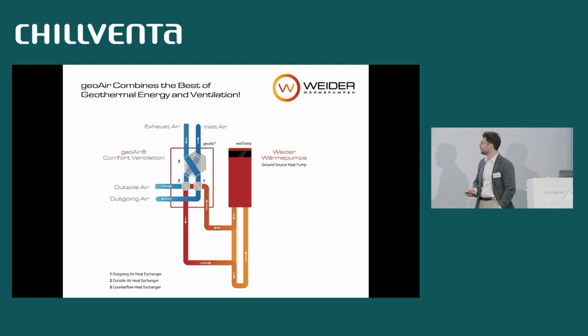You can imagine that in winter, the source temperature is usually between 0 and 5 degrees, and the outgoing air temperature is around 10 to 15 degrees. So there's quite a big delta T throughout the winter, and this enables regeneration of the heat of the geothermal source during the heating period. The second heat exchanger is a brine to air heat exchanger as well, and it goes from the outside air to the brine. And whenever in winter the outside air is warmer than the source temperature, it also raises the source temperature, and we are able to store energy in the source itself.